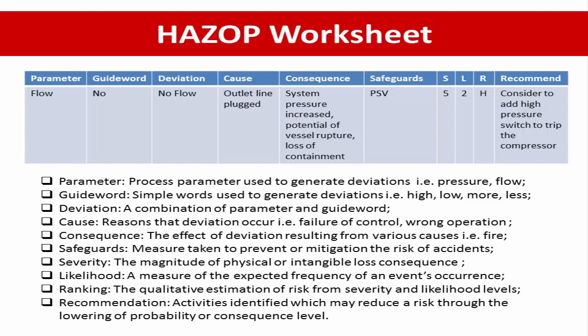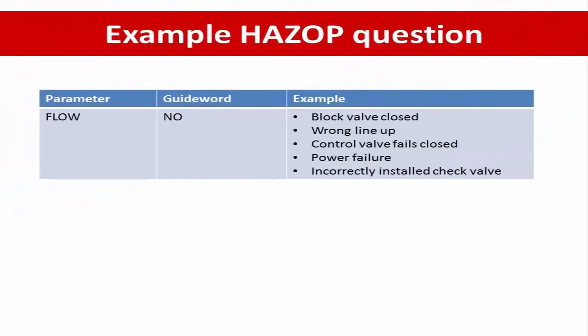When considering severity, we evaluate without relying on the safeguard — so if the system has overpressure and loss of containment, the severity rating may be 5. For likelihood, we check the experience of the team members. Then we determine the risk ranking. If the risk is not acceptable, we must provide a recommendation. Example causes for a 'no flow' deviation include: block valve at outlet is closed, wrong line-up by operator, control valve failure, power failure, or incorrectly installed check valve.